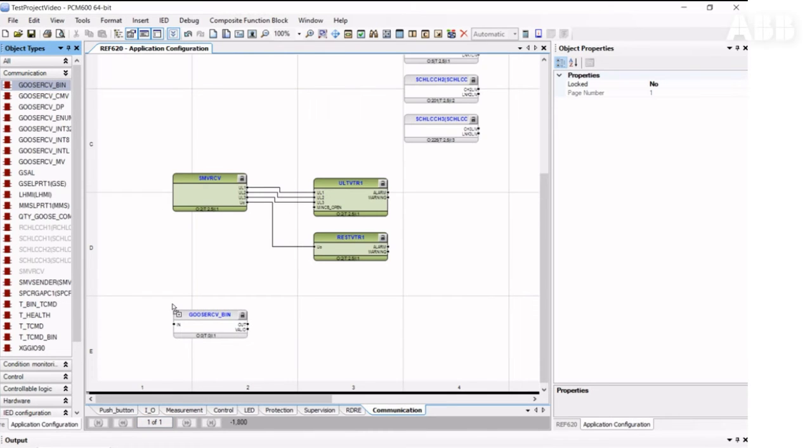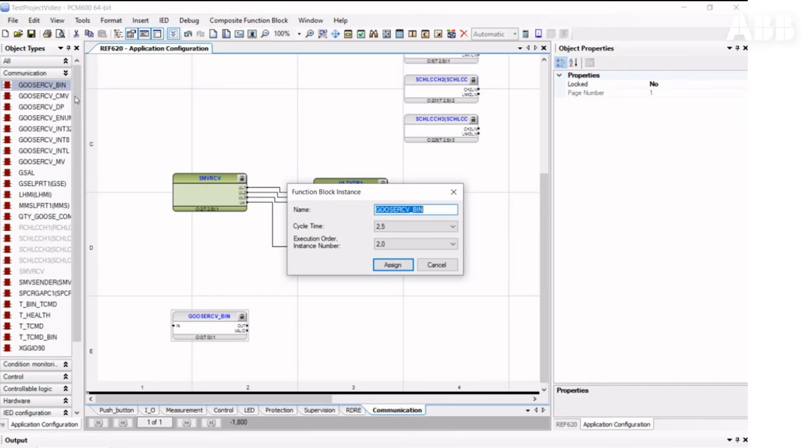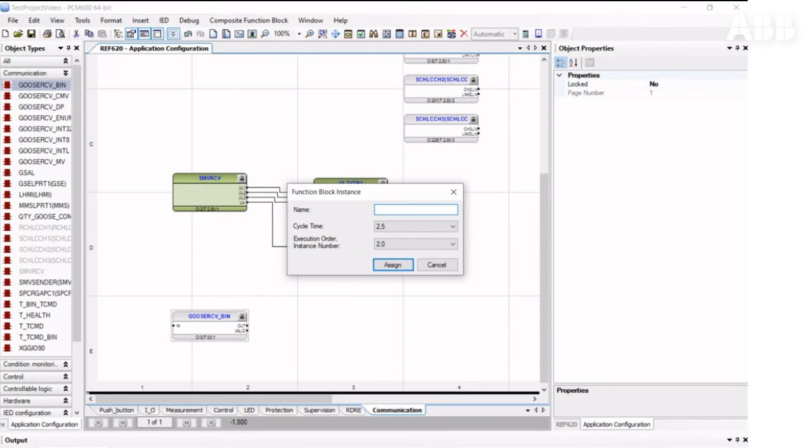We're choosing binary because we're going to receive the binary signal. Different types of signals may also be received: measured values, integer values, interlocking signals, enumerated, and double-point signals. I'm going to change its name, because in real applications you usually receive a lot of GOOSE messages from different sources, and I want to specify that this is an REF-615 overcurrent start.